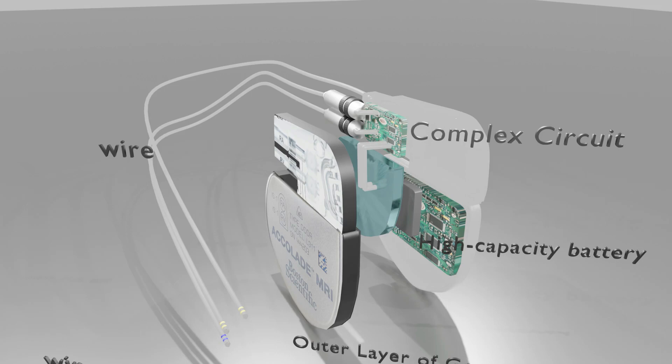The lithium-iodine battery has been the dominant power source for implantable cardiac pacemakers, which typically have peak power demands on the order of 100 to 200 microwatts. Under these conditions, the lithium-iodine battery can maintain an adequate voltage even when its internal resistance reaches several thousand ohms. On the other hand, an implantable cardiac defibrillator may have peak power requirements approximately 10,000 times greater than those of a pacemaker. Under such a high power demand, the voltage of a lithium-iodine battery would drop to almost zero, and the power delivered to the device would be almost nil.